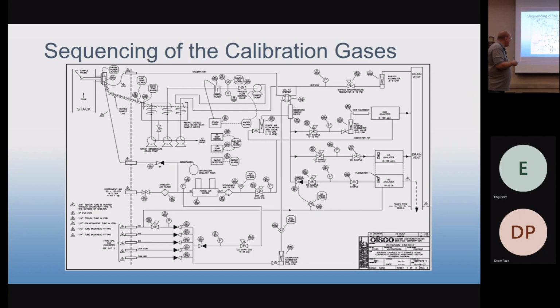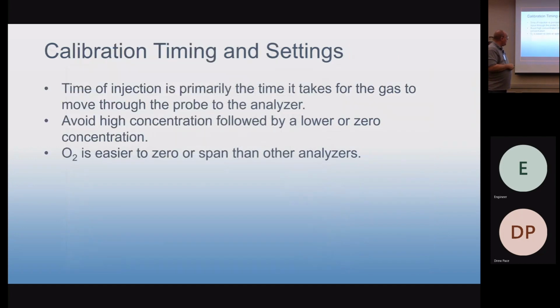Oh, no, you're fine. So what we would do is we'd start with the nitrogen. Everybody goes to zero, including the NOx, the CO, O2. All the analyzers got their zero off of that nitrogen. And then they would run what I call the pollutant gases, the NOx and the CO, and get whatever ranges we had for those, starting with the low range and working to the high range. And then we'd end up with the instrument air or O2 cylinder, whichever you have. And the reason for that is, while some analyzers have trouble going from a high concentration to a low concentration, the O2 analyzers we use do not have this problem.